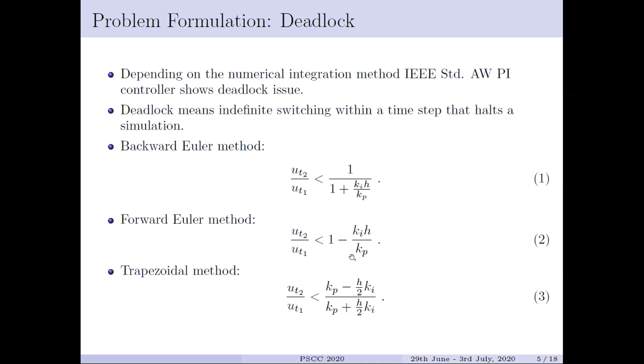Now, there exist several techniques to avoid or solve this issue. The first solution is using a deadband. This technique modifies the state transition diagram and introduces a deadband here. To move from the integration state to the maximum state, the controller output has to be greater than the maximum value. However, to come back from the maximum state to the integration state, the controller output has to be lower than the maximum and also the deadband value.